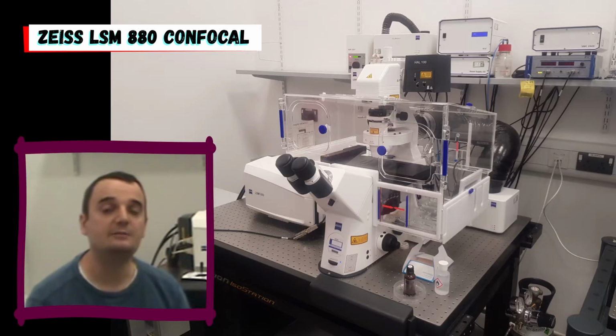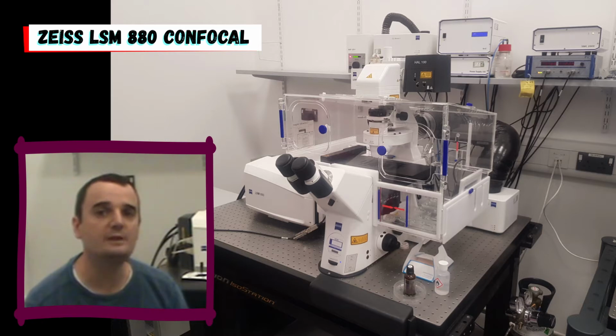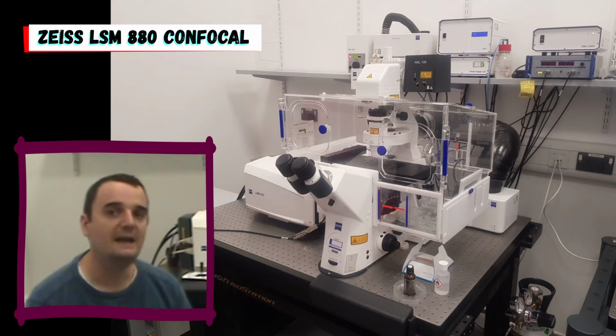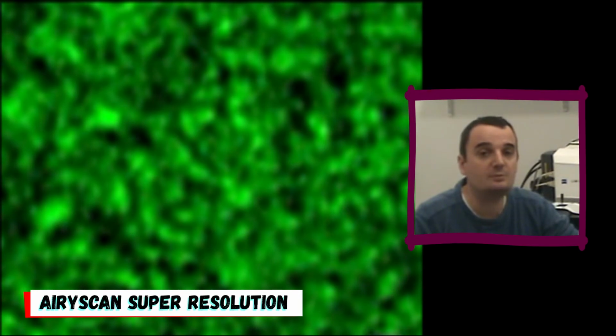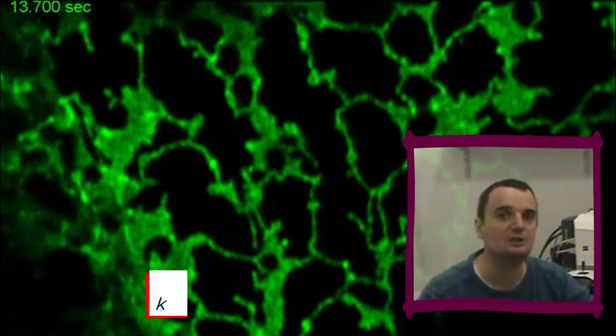Its scan speed is really fast, and it's equipped to do something called super resolution imaging with an Airyscan based approach. The images that you're seeing now are from plant plasma membranes, and these are nanodomains that are only visible with super resolution techniques. They are not visible with normal confocal microscopy. And the example you're seeing now is a plant endoplasmic reticulum, which is being imaged very quickly with the Airyscan fast system, and you can see you have a really fantastic image.